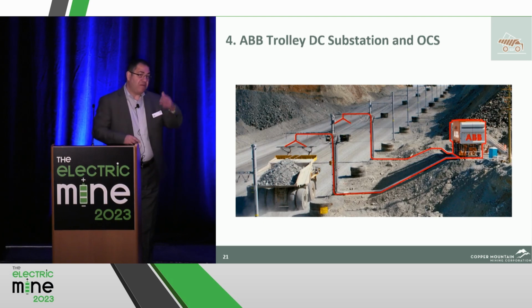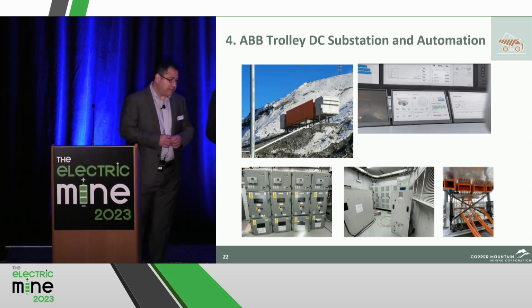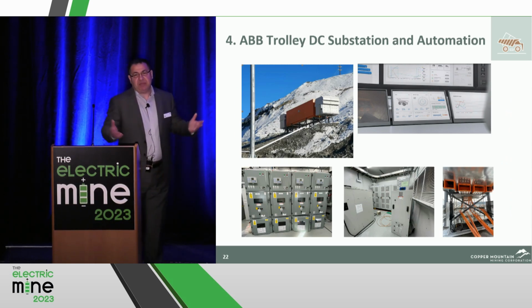So our supply included the DC substation as well as component on the OCS. Copper Mountain took over the construction to our design. Inside the substation, your typical AC switchgear, DC rectifiers, DC switchgear, and then the rectifier transformers outside. This is kind of what we call the DC substation, and there's a control system that monitors the performance of the electrical power supply.